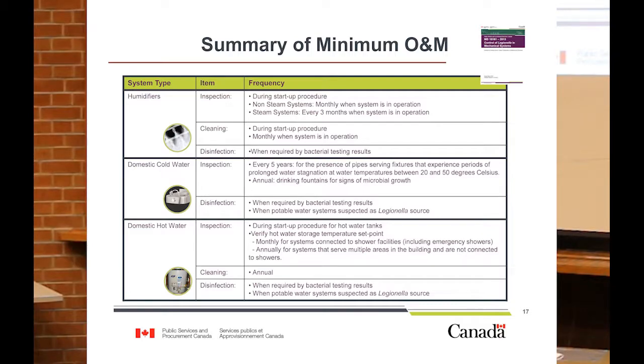On the humidifier side too, we have differences in maintenance requirements based on whether the humidifier is a steam-based system, so high temperature where you're getting bacterial kill, or a non-steam system like an adiabatic unit that could be operating in the growth temperature range for Legionella. On the domestic cold water side, again, we have inspection requirements. The main focus here on the potable water side is to make sure that we don't have dead legs in the system, eliminating those dead legs.